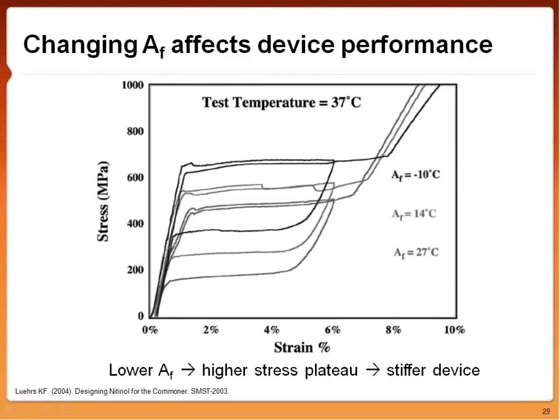You can see that in these typical flag nitinol curves over here. So the take-home message from this is the lower AF you have, the higher stress plateau you're going to have, which means the stiffer device you're going to have. And that, again, is controlled by the type of alloy you're using and how much nickel is inside your matrix. So, again, if we think of these being SE508 material, what really happens for how much nickel we're taking in and out of that parent matrix?